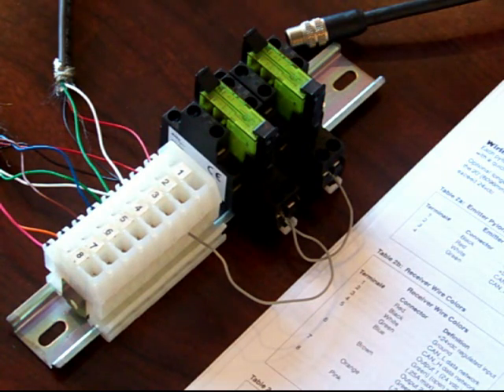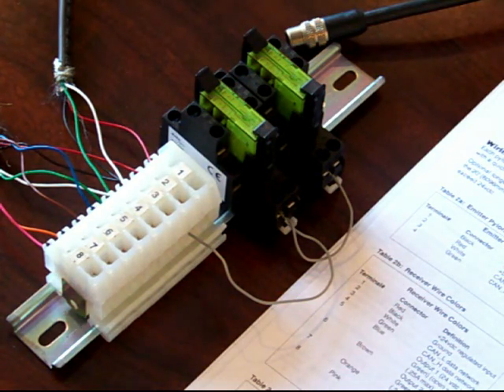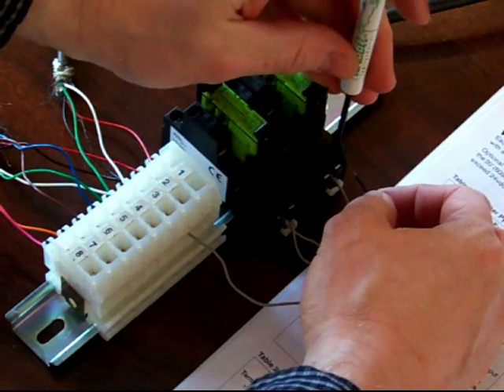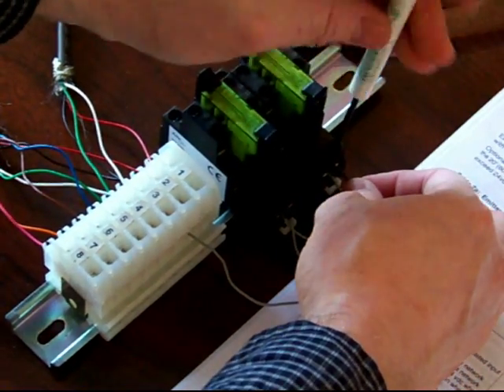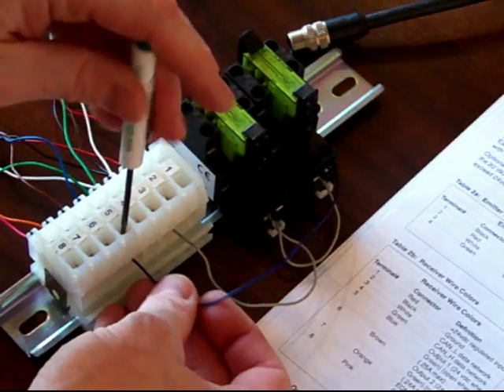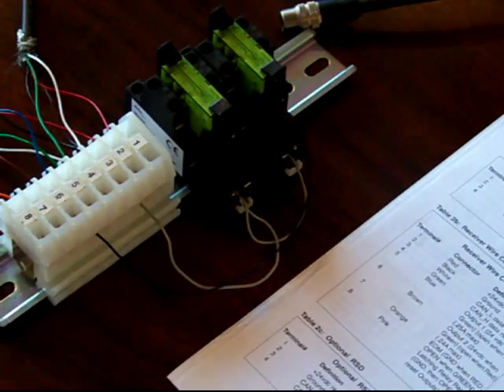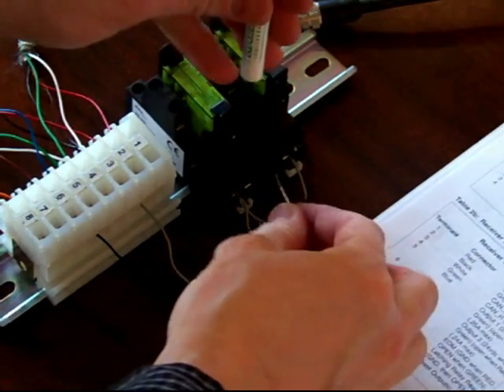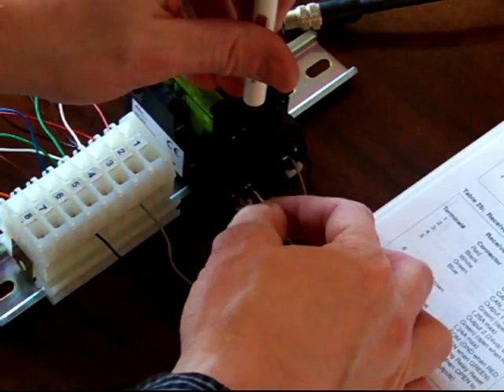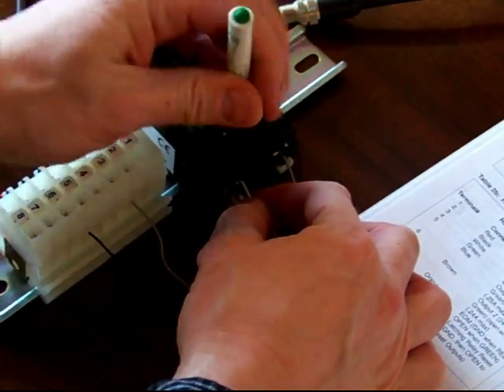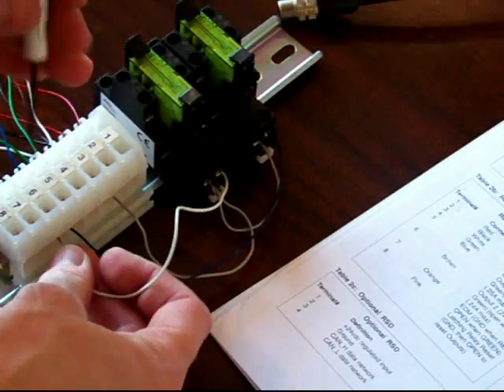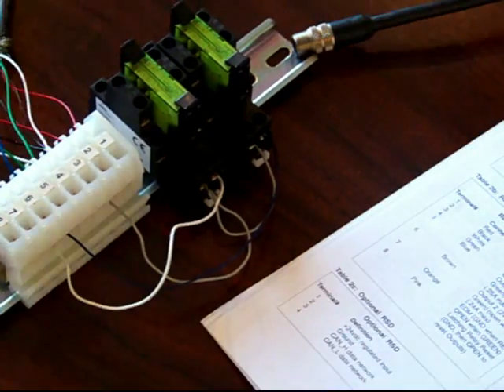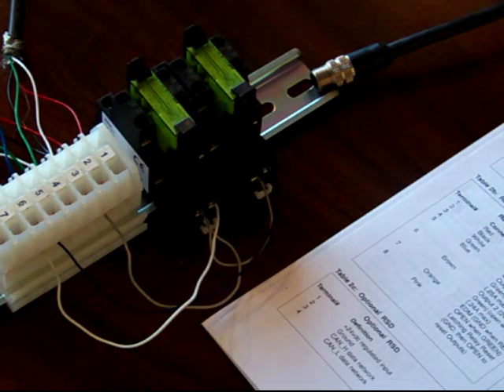One of the safety relays, the A2 terminal, gets wired over to the blue wire, which is terminal 5. A2 of the other safety relay gets wired up to terminal 6.